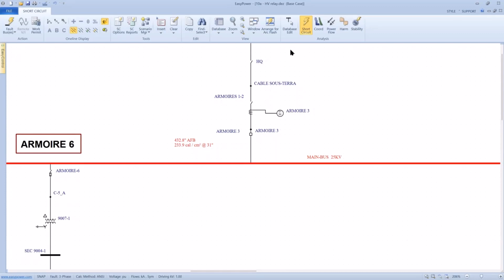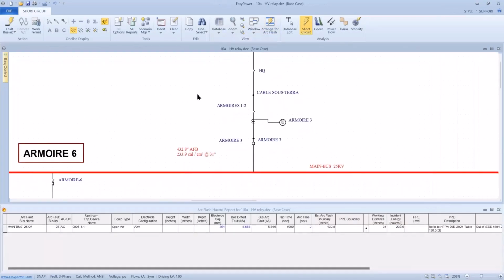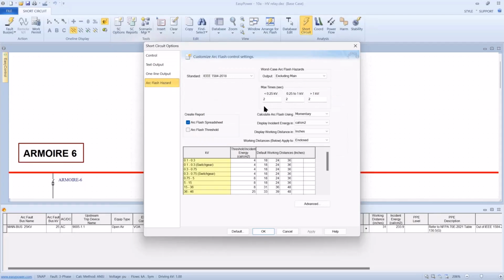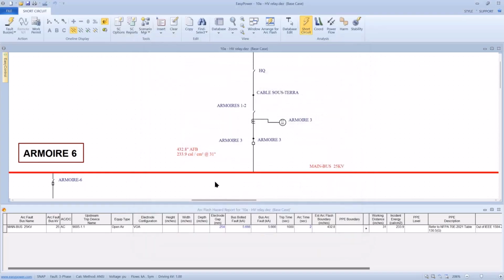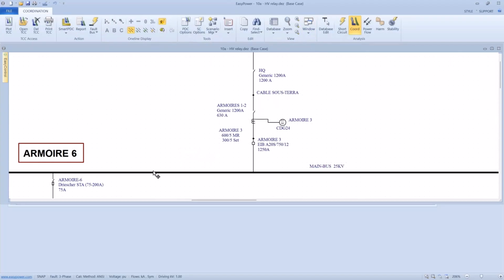Well, the first question that I asked was, what is faulting? What's even giving us that time? And if we look at our short circuit options, he already had his time limit set up to 2 seconds. So that made me nervous and concerned about coordination. When I go to the arrange for arc flash, I see that the upstream trip device is 9005.1.11. And the next question was, what's the sequence of events telling me? So if I pick out a single bus, fault the bus, and then look at sequence of events, this relay is tripping at 16 milliseconds.